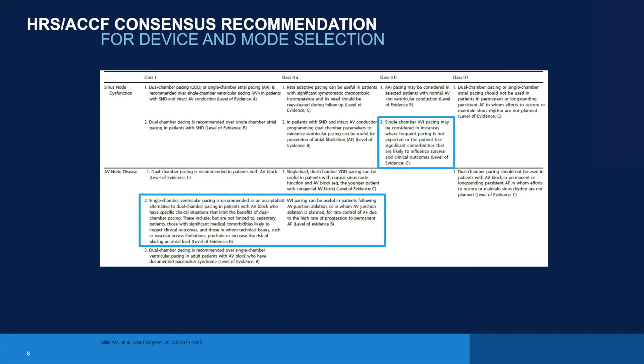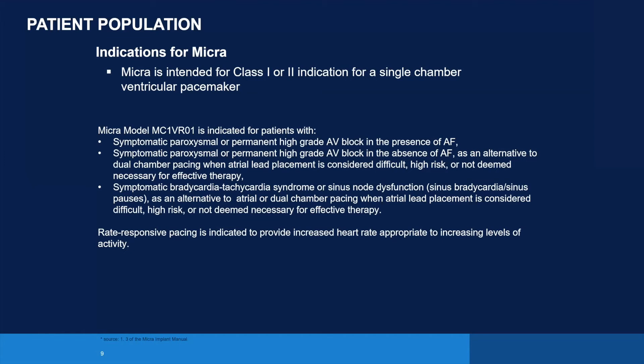So the Medtronic Micra, the leadless pacemaker we currently have available, is intended for class 1 or class 2 indication for a single chamber ventricular pacemaker. So that's the important concept there, this device is only a ventricular pacemaker. And the common indications are symptomatic paroxysmal or permanent high-grade AV block in the presence of atrial fibrillation. So we've been talking a lot about atrial fibrillation. If someone has atrial fibrillation with heart block, there is absolutely no need for an atrial lead, as they do not require any pacing or sensing of their atrium. Similarly, it can be used as an alternative to dual chamber pacing when atrial lead placement is considered difficult or the patient is considered high risk.